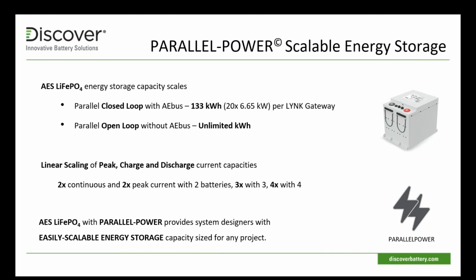The advantage that we have here is that our ability to do peak charge, continuous charge, and discharge capacities scale very, very easily. You have 2 batteries, it's 2 times. You have 3 batteries, it's 3 times that. This is because we have a BMS on each and every battery, and they communicate with each other. So we're able to do this. We don't require a centralized BMS system or anything like that. Again, this really makes it very easy to install when you compare it to some of the other rack-mounted and enclosure-based systems.